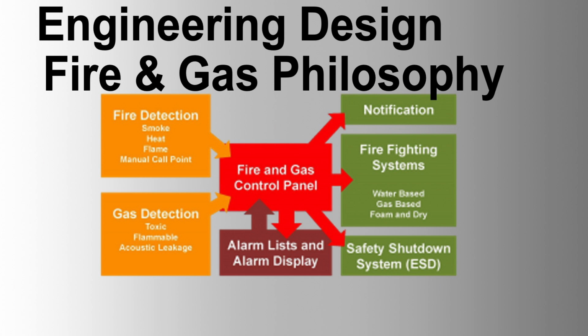Availability and reliability. The reliability and availability of the fire and gas system are critical. The system should ensure autonomy of fire and gas operations, minimal effect of single component failures on overall availability, full redundancy on all inputs-outputs, use of proven technology and redundant power supplies, an assumed mean time to repair, MTTR, of 4 hours and availability greater than 99.999%.